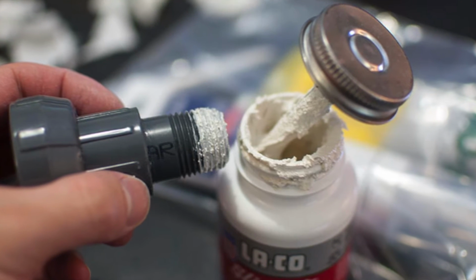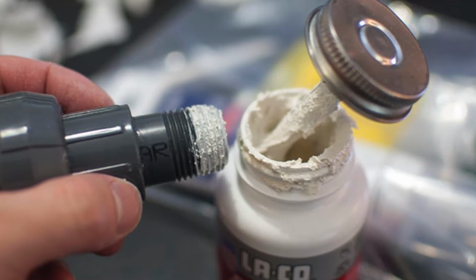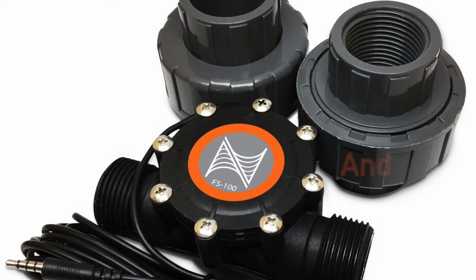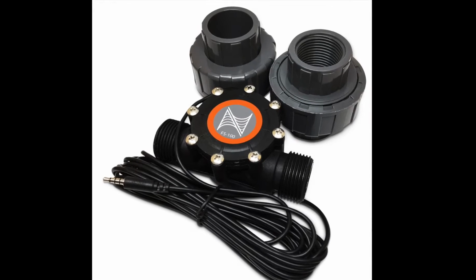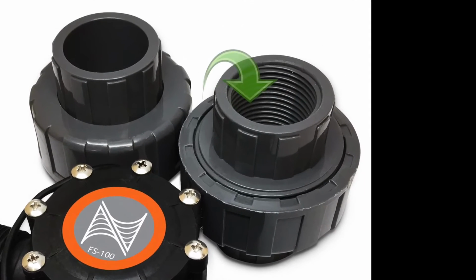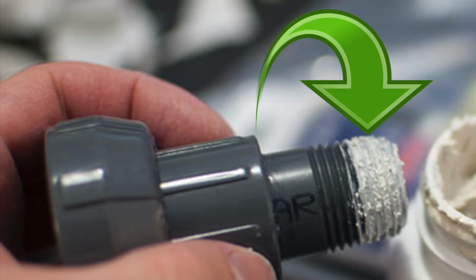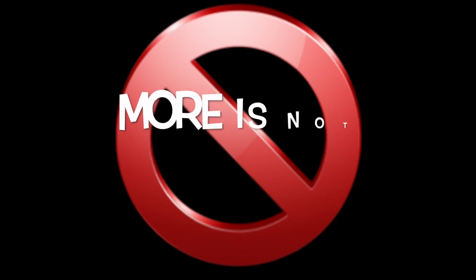When using the thread sealer paste, you can apply it to either the ends on the flow sensor and the female threads on the unions. Only apply the sealant to the first 4 to 5 threads of the female and male fittings. But you do not want to use an excessive amount. More is not always better here.